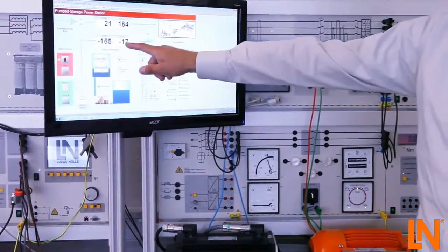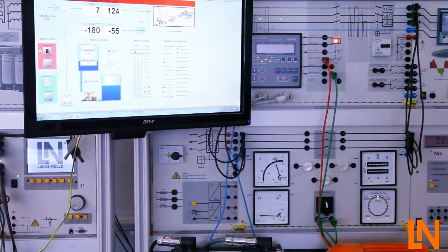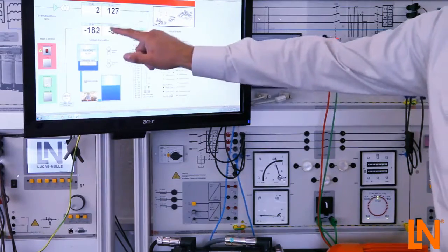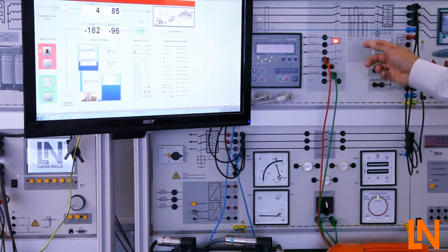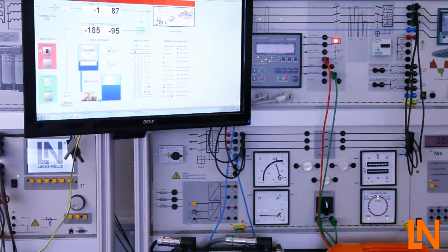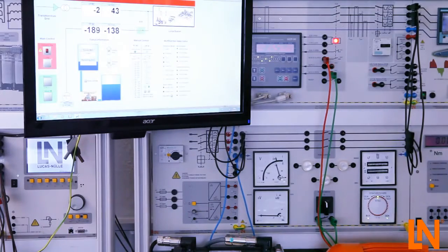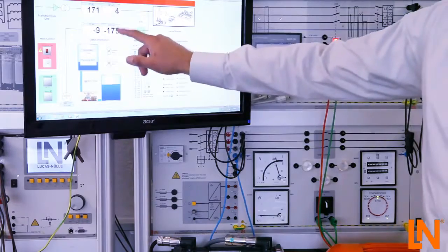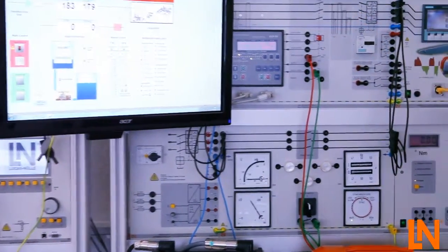And here you see that it automatically generates the power which is needed, and as well the control of the reactive power is also made by this multifunction relay. As well as protection of the generator, many functions like over voltage, under voltage, frequency control, over current are integrated in this device so that this works totally automatically and protected as well. So now I can stop the device, and the power goes down, and after the power is going down, it would be switched off.